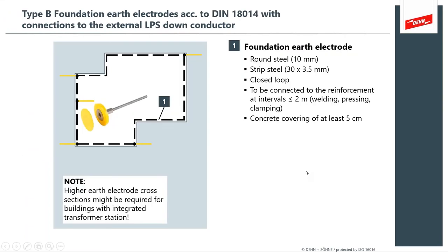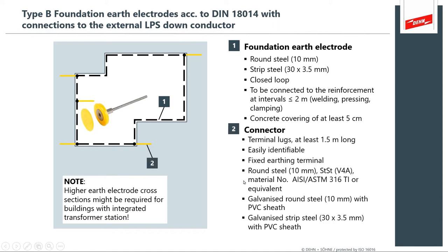Foundation earth electrodes. We know that we're looking for things like the closed loop. We're looking for the embedded connections so that you have points where you can access that earth electrode. We're looking for connections that are easily identifiable. We're looking for galvanized materials that are resistant to corrosion.